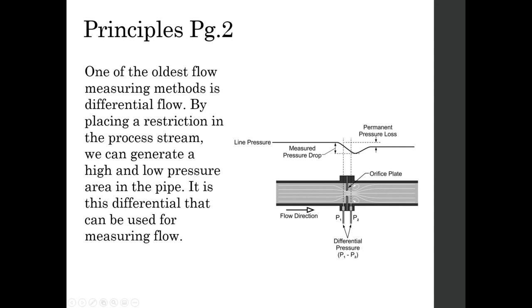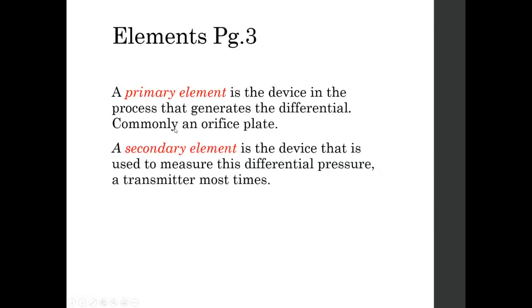We're focusing mostly on elements in this ILM. A primary element by definition is the device in the process that generates the differential — commonly an orifice plate — but we're not speaking about orifice plates in specific terms in this ILM, although there is a section at the back from the previous version that I decided to keep in because orifice plates are so common. The secondary element is the device used to measure this differential pressure, and most times it's a differential pressure transmitter.